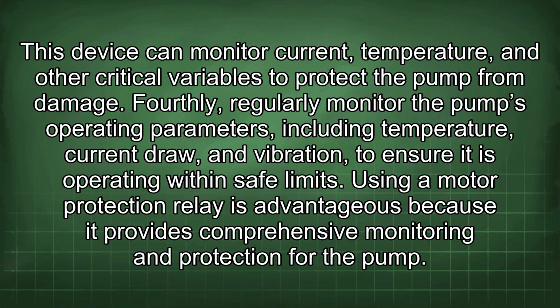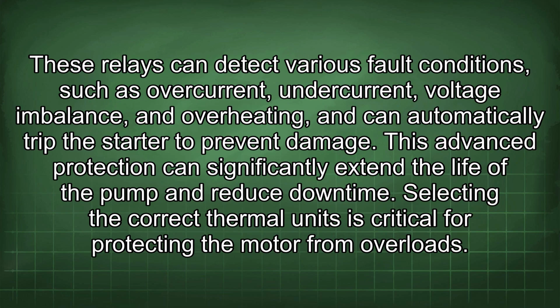Fourthly, regularly monitor the pump's operating parameters, including temperature, current draw, and vibration, to ensure it is operating within safe limits. Using a motor protection relay is advantageous because it provides comprehensive monitoring and protection for the pump. These relays can detect various fault conditions such as overcurrent, undercurrent, voltage imbalance, and overheating, and can automatically trip the starter to prevent damage. This advanced protection can significantly extend the life of the pump and reduce downtime.